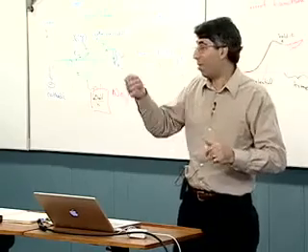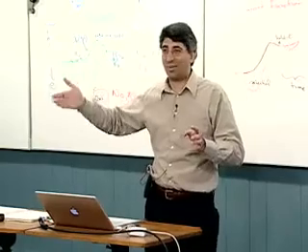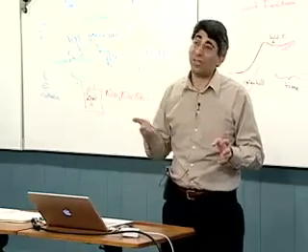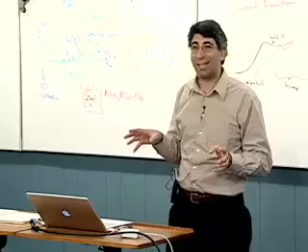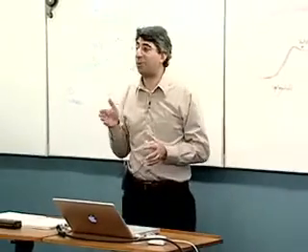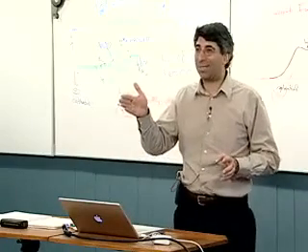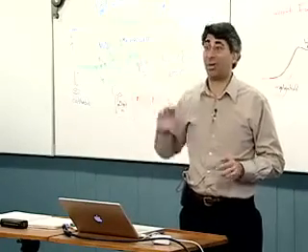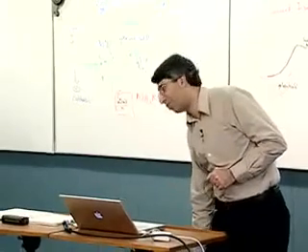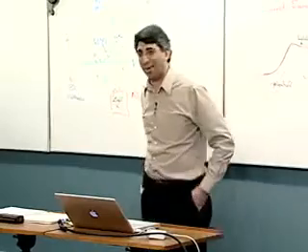That is, there are knobs or buttons on them that let you go, you know, at 10 or 100 or 1,000 volts per second, and yet actually the electronics in the potentiostat can't necessarily keep up with that. That is, you may be able to ramp your power supply at that rate, but that doesn't mean that your current following can occur at that rate.